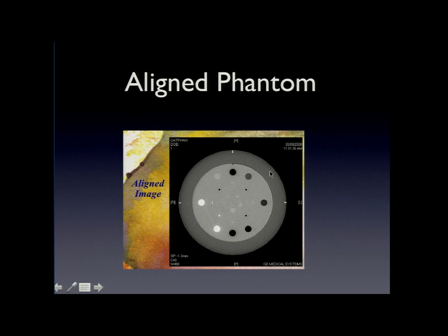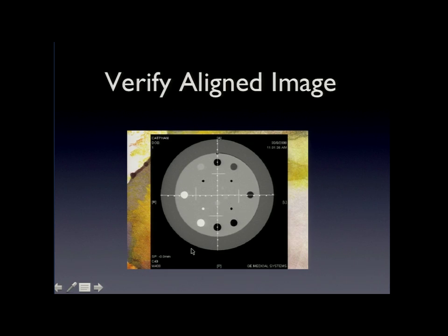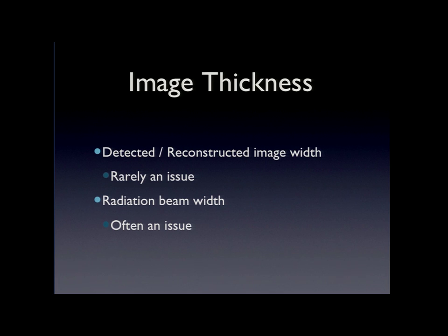It's the same method that you do with the ACR Phantom. It has the fiducial markers here, so you can see it straight, and then you can tell that you're positioned. You can also bring up the grid just to make sure you're centered. You use the measurement tools within there, and you verify that your phantom is aligned.